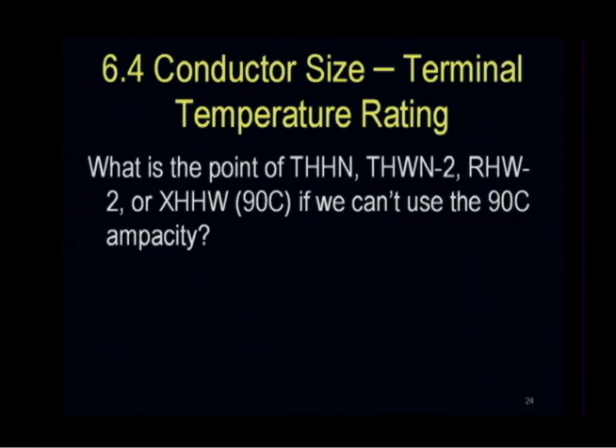What's the point of THHN, which is 90-degree C? THWN-2 — the suffix dash 2 means 90-degree C. RHW used for photovoltaic systems, dash 2, or XHHW — all of these are 90-degree C. But if we can't use the 90-degree C ampacity, why do we have it?